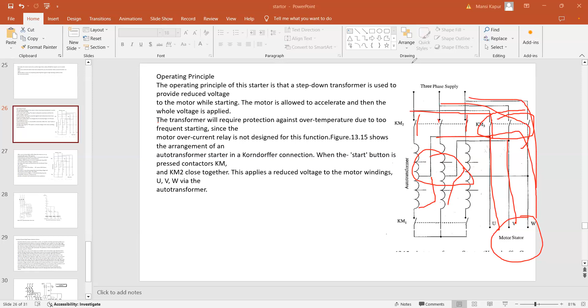So first, what will happen? This phase is coming from here. This circuit will complete from here, KM2. And you are taking a tapping from here and reducing the voltage. So obviously the voltage will go from here. Now suppose your motor is already started and you shifted the transformer slowly to the same voltage. Once it is on the same voltage, if you close the KM3 also, you can apply the same voltage which is coming from top, right? And your auto transformer is isolated, right? Understood the circuit now?